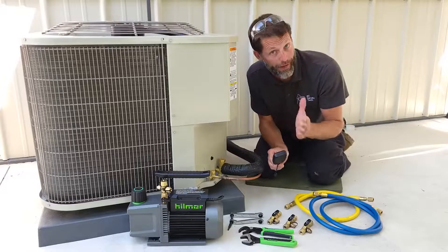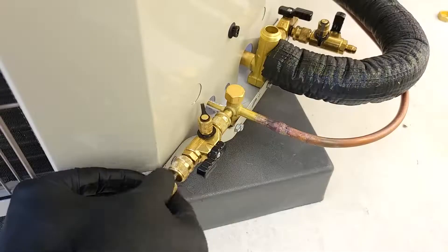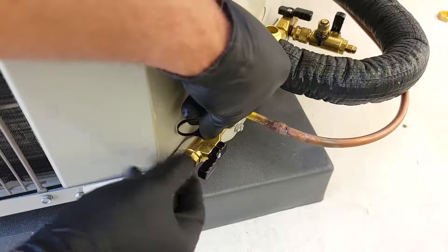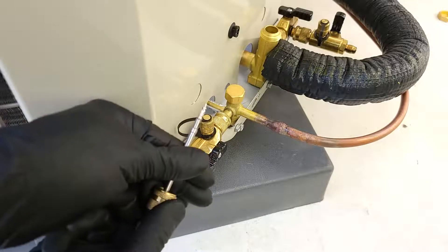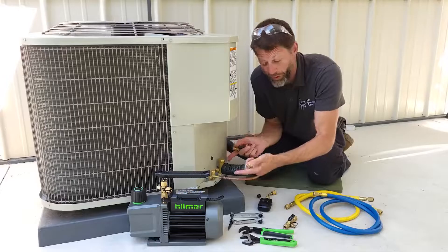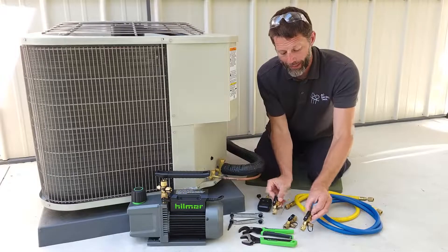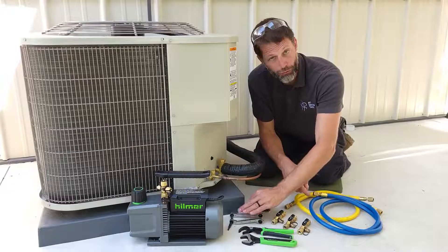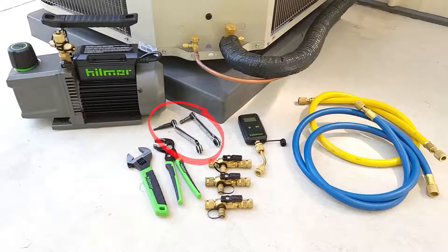We need to get a vacuum below 500 microns. We're going to be using valve core removal tools because these are rated down to 20 microns in order to hold the vacuum. We're also using these to pull out the valve cores so they are not an obstruction while we're pulling our vacuum, and I use three valve core removal tools. I also like to utilize two ratcheting service wrenches, and then we just have our holdback adjustable wrench and pliers.